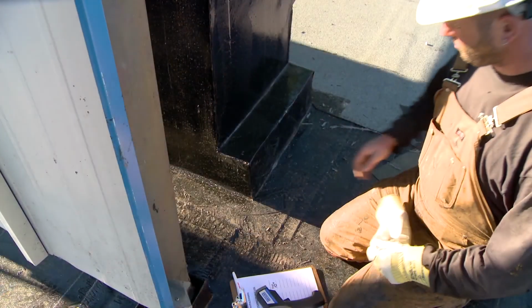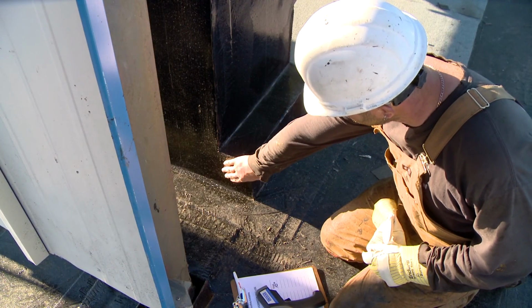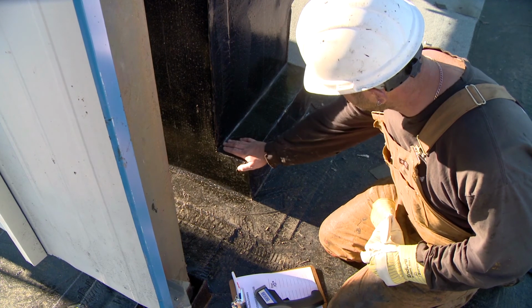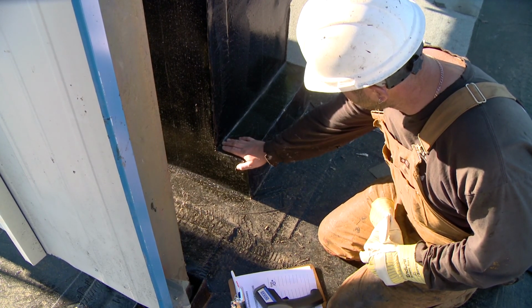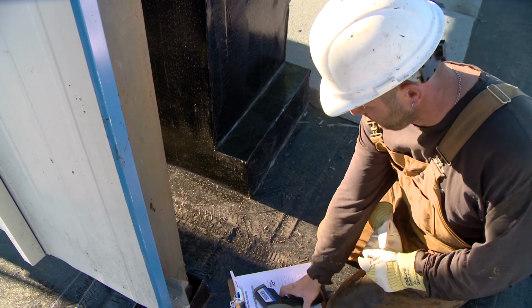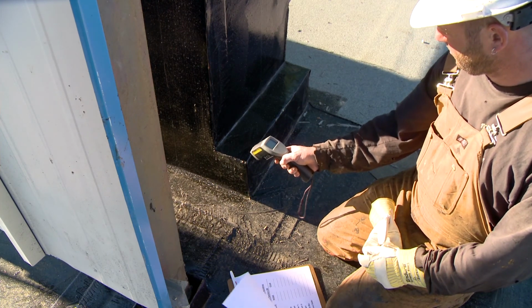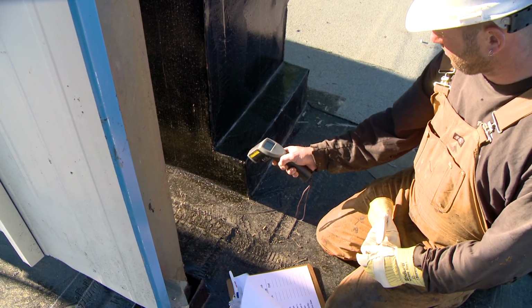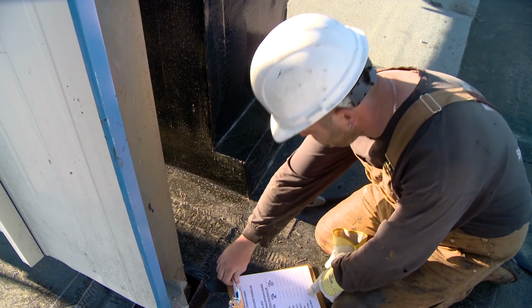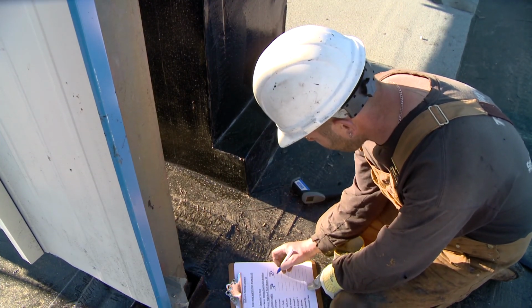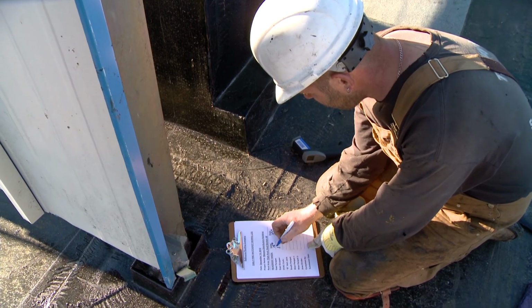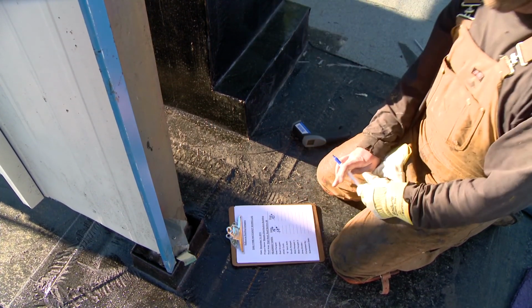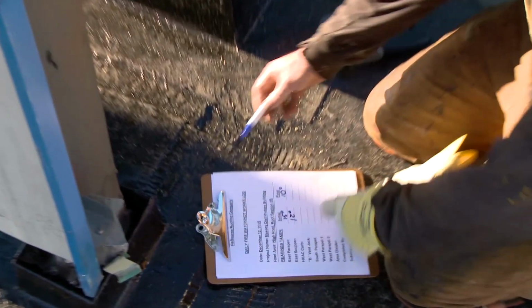The recommended fire watch duration for new construction is a minimum of 1 hour, unless the specific duration is required by the contract documents. When re-roofing, additional fire watch times may be required, as the building may be more susceptible to hotspots and fires. During winter, it is recommended to terminate torching operations in the afternoon to permit completion of a fire watch during daylight hours.